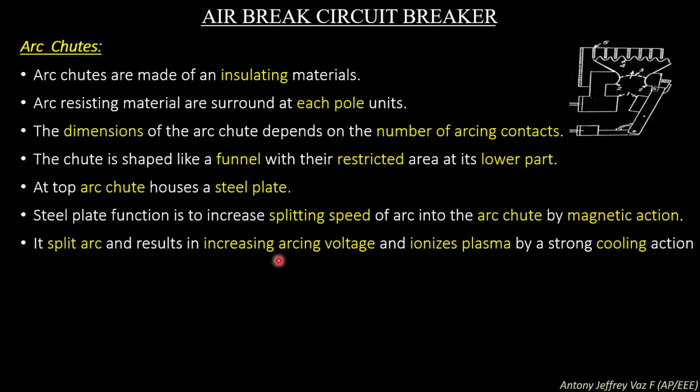The metal plate splits the arc, resulting in increased arcing voltage and ionized plasma being subjected to strong cooling action. The outer section metal plate is in contact with fresh cold air from the atmosphere and radiates coolness into the circuit breaker. The arc chutes and metal divider plates cool the arc effectively. Since the arc is cooled, the arcing voltage between the two contacts increases, but due to splitting of the arc, this increased arcing voltage cannot be maintained for a longer period and the arc gets extinguished easily.